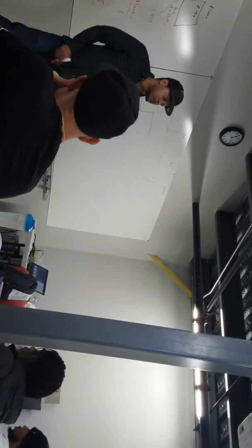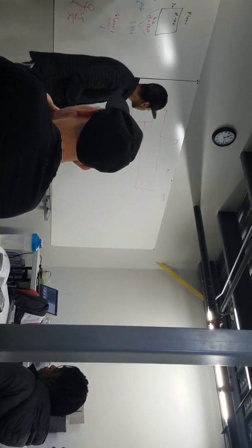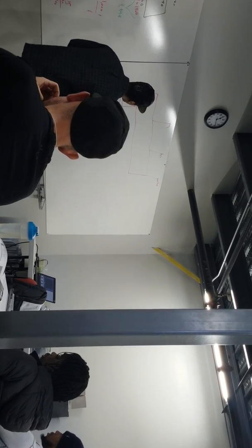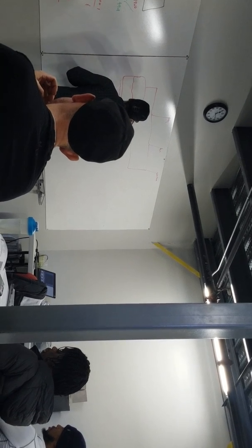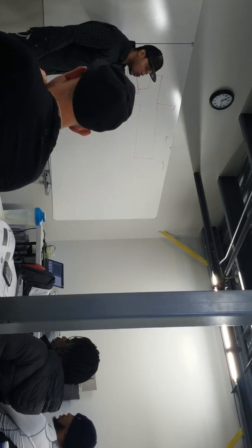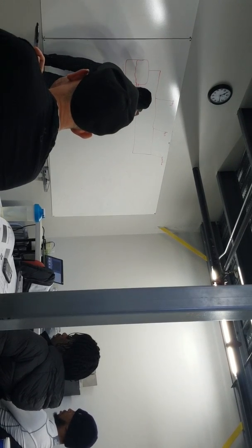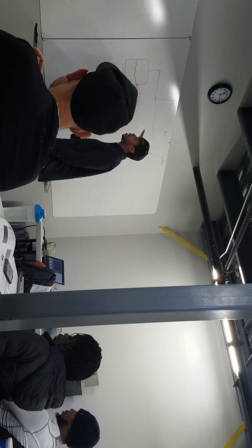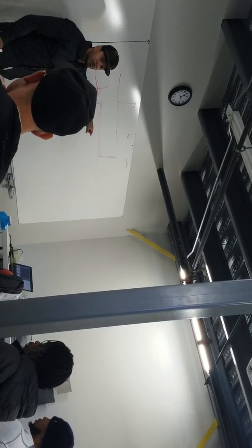So a company, an insurance company in Hartford, Connecticut, somebody on the team came up with a solution. He said, well, since the problem is that boilers run out of water, couldn't we add a loop on the return side? So that way the water level would never fall below the loop. Right? So even if the boiler ran out of water, it will only run out to a certain degree because of this loop back here. It would keep the water level lined up with this loop. And that's the Hartford loop. That's specific to steam systems.